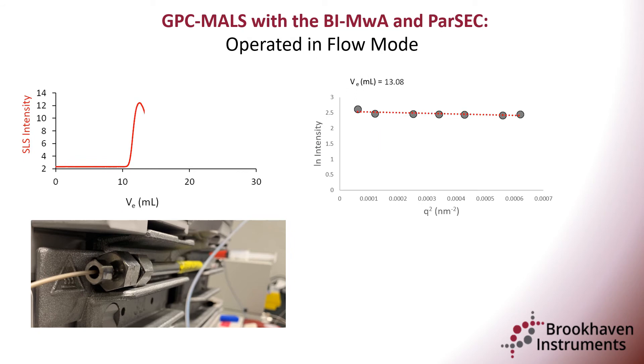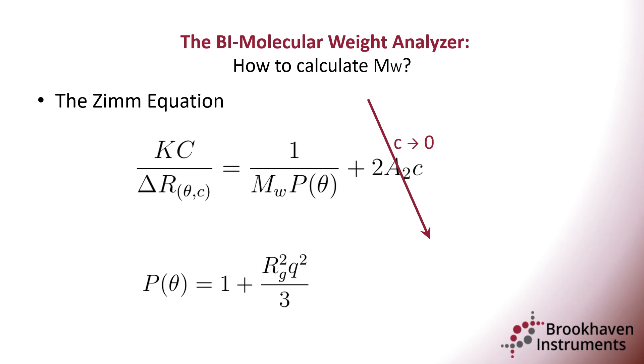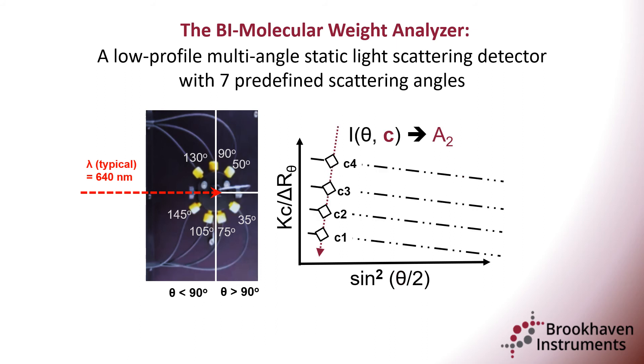The light scattering trace can be expanded to show static intensity from each angle separately. As with any SLS measurement, using the Zimm equation to measure molecular weight requires a double extrapolation. At the limits of both zero concentration and zero angle, the scattered intensity depends only on the absolute molecular weight of the sample. In a MALS experiment, the light scattering trace is actually made up of a continuum of angle-dependent measurements, where each point in the chromatogram corresponds to a different instantaneous concentration. Thus, a single measurement provides all the information necessary to calculate an absolute molecular weight.